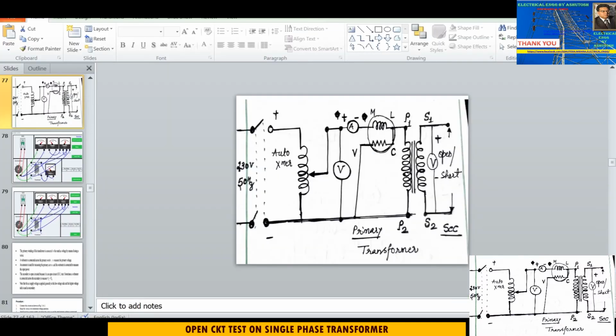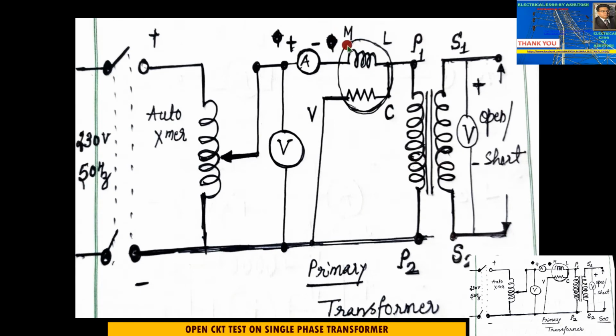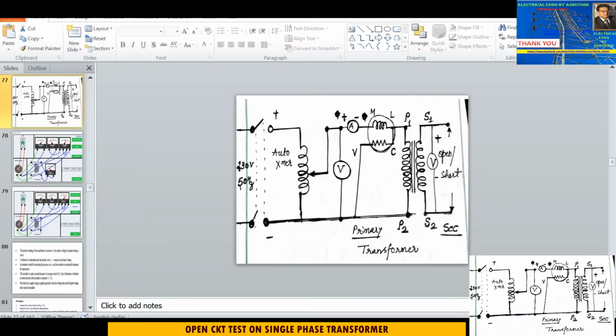Now see the second step, how the wattmeter is connected. There are 4 points on this wattmeter. M means mains, connected to the mains. L means load, C is the C point, and V means voltage coil. Here L and C, the 2 points, are short circuited. These are the combined points, L and C. M is connected to ammeter's minus. As you can see over here, M point of wattmeter is connected to negative of ammeter. L and C are short circuited, and V is connected to this point, P2, the lower point. So now you can connect. Just follow this.